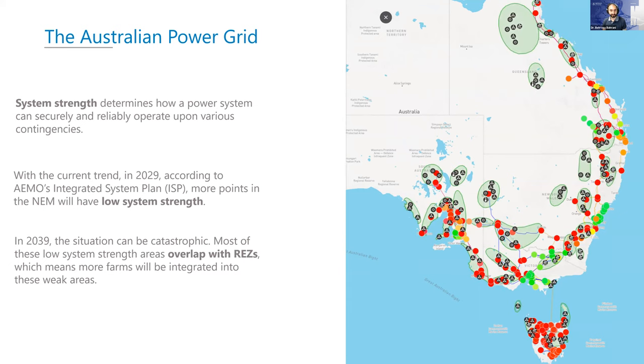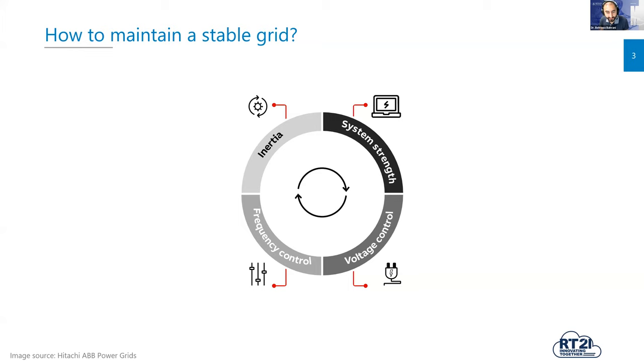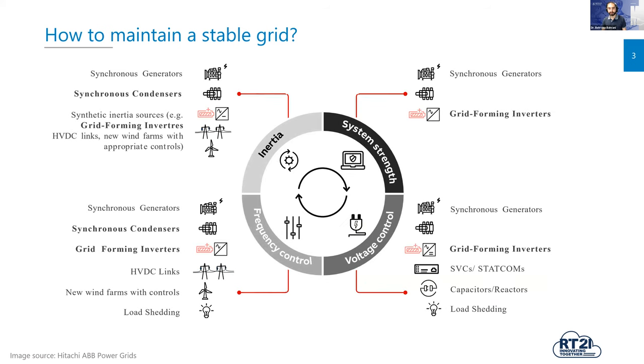There are four pillars required to maintain a stable grid: system strength, voltage control, frequency control, and inertia. Different equipment delivers these services, and synchronous generators used to deliver all of them. With retiring synchronous generators, we need more innovative ways of providing these services. Grid-forming inverters in particular are one of the most promising assets, potentially capable of providing all of these services in the future. Synchronous condensers are also gaining popularity, but inverter-based technologies and IBRs are the way to go. At Monash, the focus is on various technologies around IBRs and grid integration of renewable energies, looking at two types of inverters: grid-following and grid-forming.